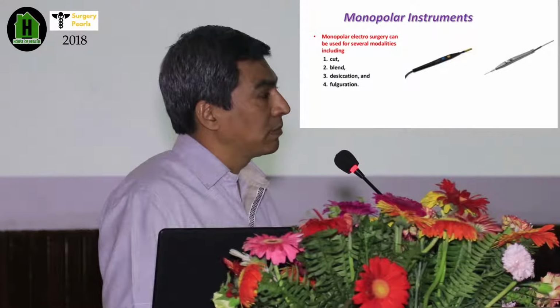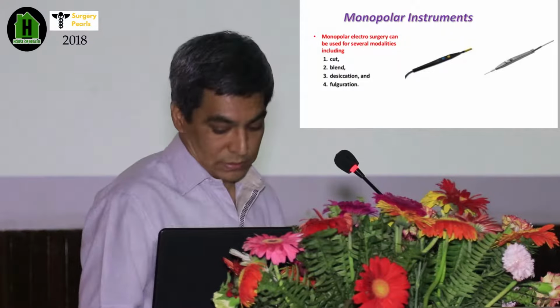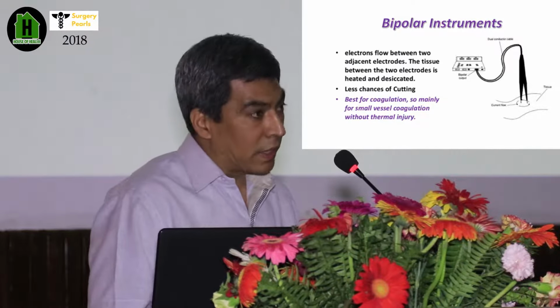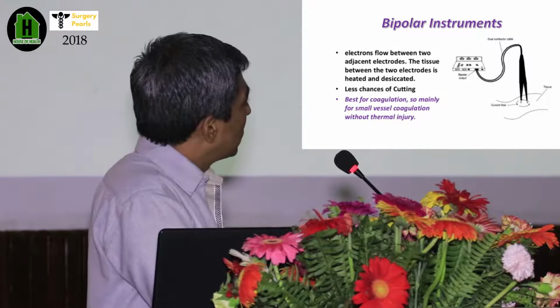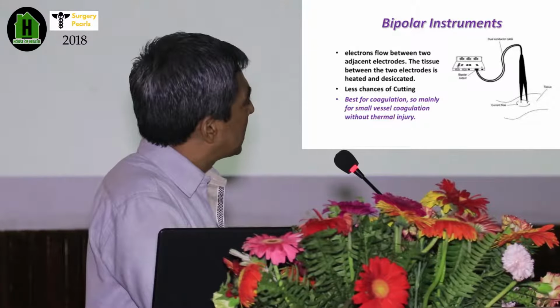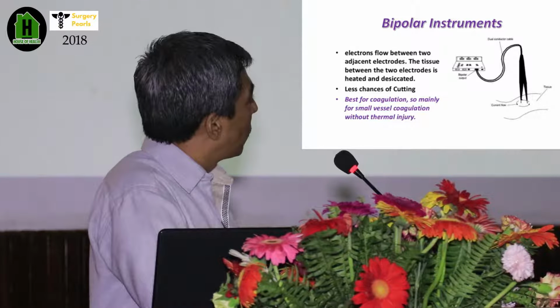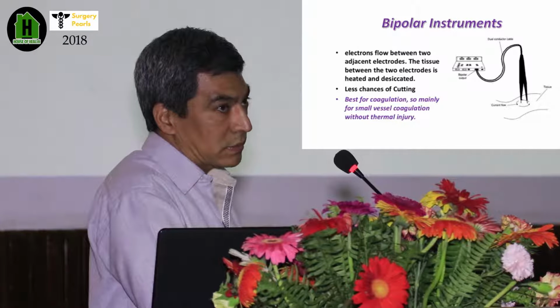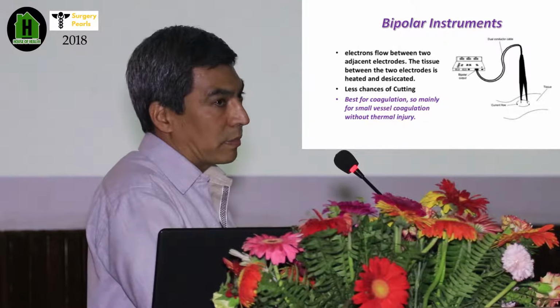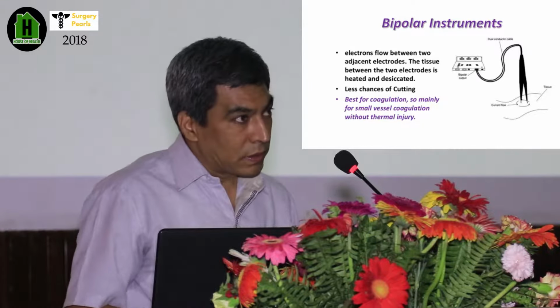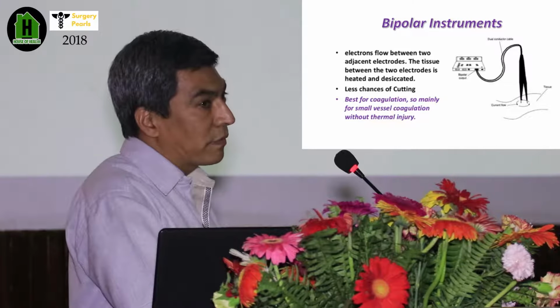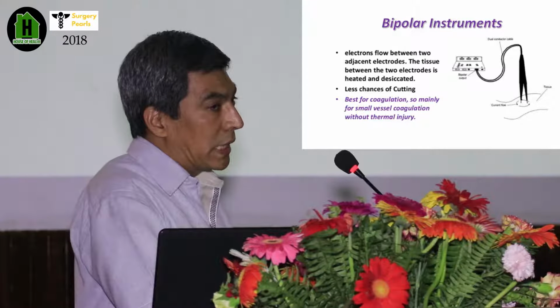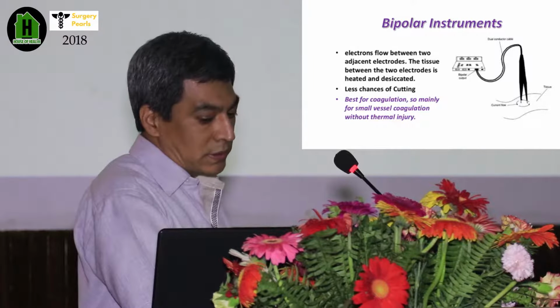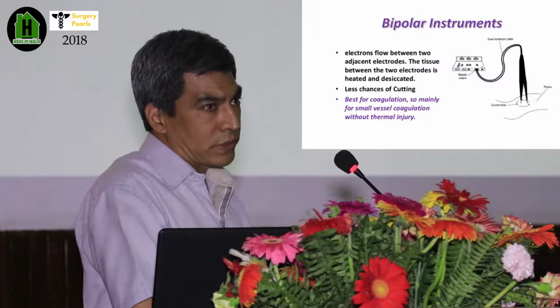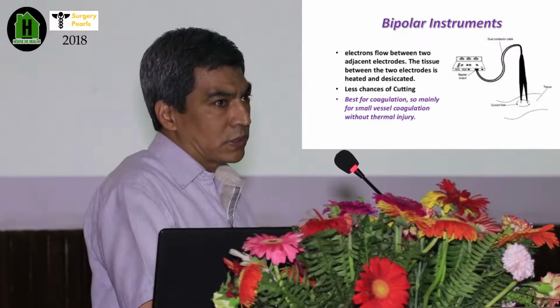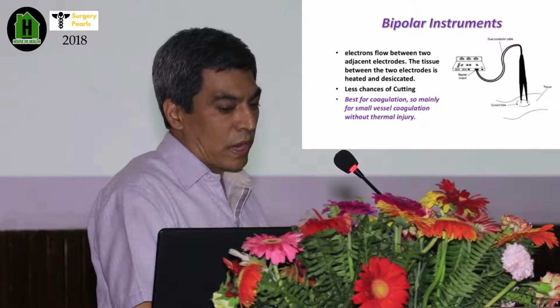Blend is nothing, it's just a mix of cutting and coagulation. It's the hybrid. Again, in the bipolar, as shown in the pictures, there are two electrodes, active and passive, at the same time. So the electricity is passed only between these two electrodes. There will be no effect at all in other parts of the body. Because there is very small current flow between these two electrodes, the voltage is low, so it can't give the cutting effect. It can hardly give a coagulation effect only.